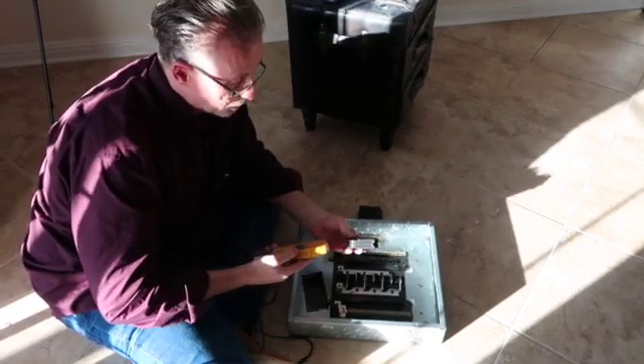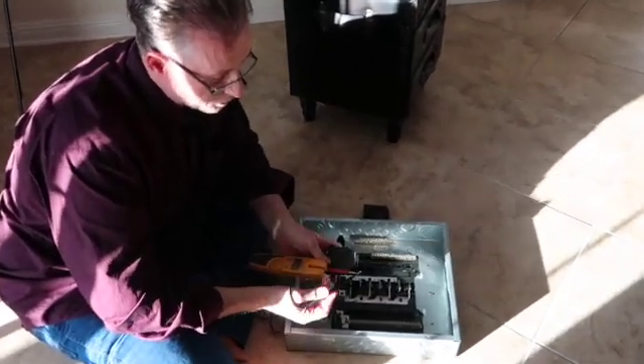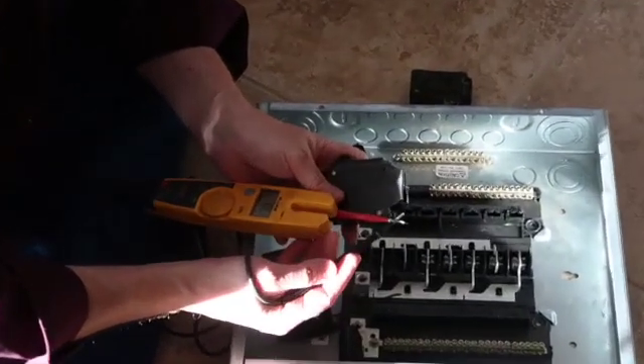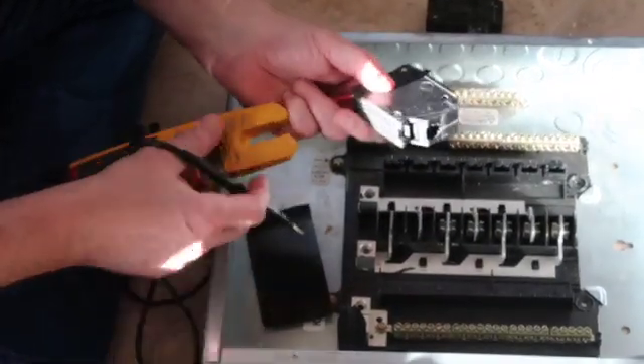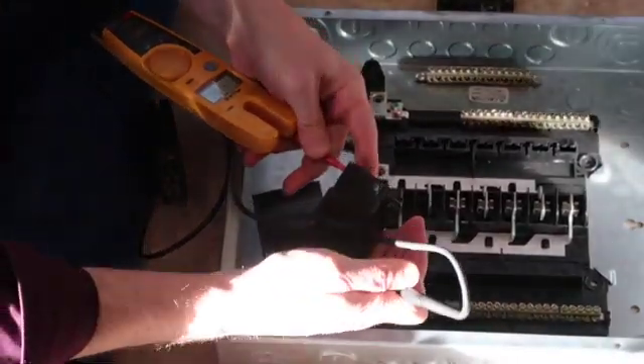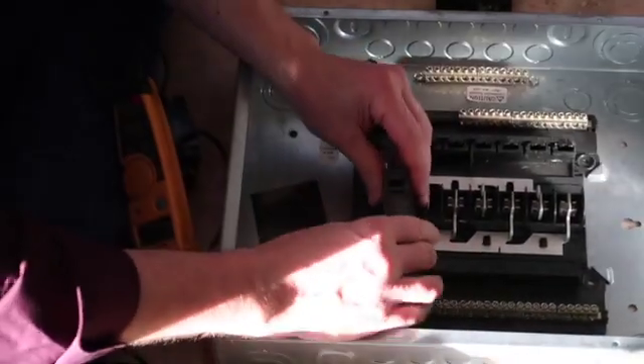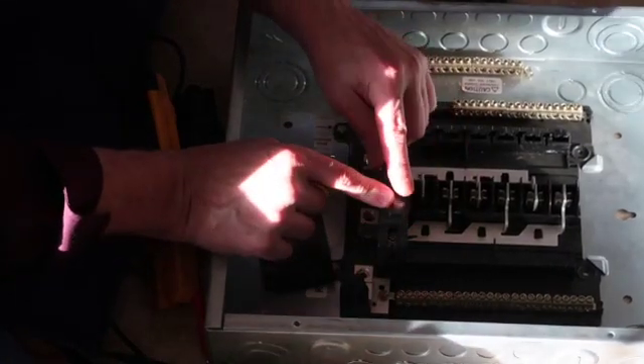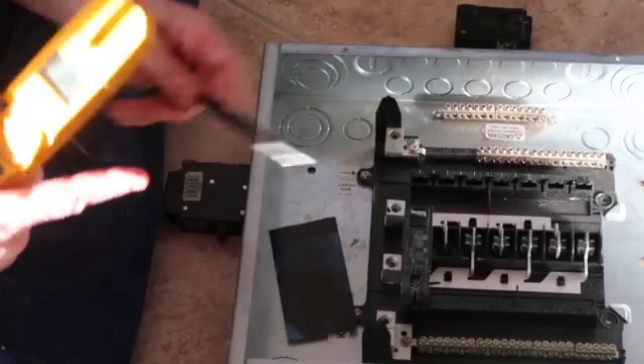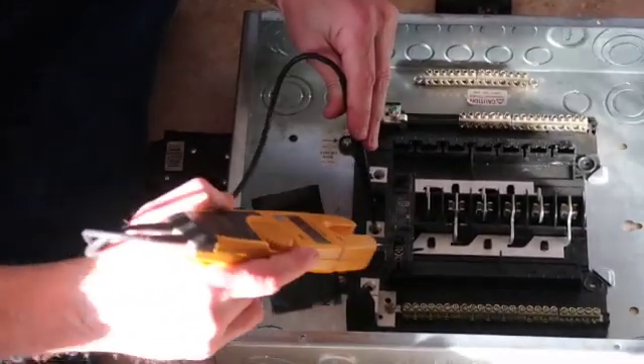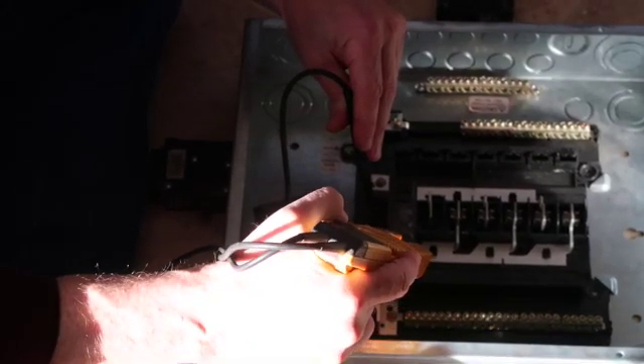So let's see what we have here. First you always test your meter to make sure your meter is working. This one's beeping. It says there's one ohm between the wires. One ohm resistance. Resistance is the opposition to current flow. This one's working, I can hear it beeping. This one works. Now so what would happen is this would go here. You click in here and you always put them in on the off, and then you turn it on. So now we should have conductivity or continuity between the hot wire and also here. And you can hear now it is beeping, which means that this breaker is ready to feed and protect whatever it needs to protect down the line.